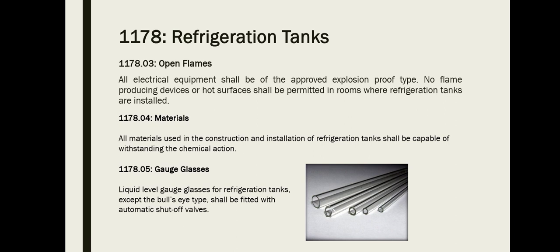Rule 1178.04, Materials. All materials used in the construction and installation of refrigeration tanks shall be capable of withstanding the chemical action. Next is Rule 1178.05, gauge glasses. Liquid level gauge glasses for refrigeration tanks except the bull's eye type shall be fitted with automatic shut-off valve.